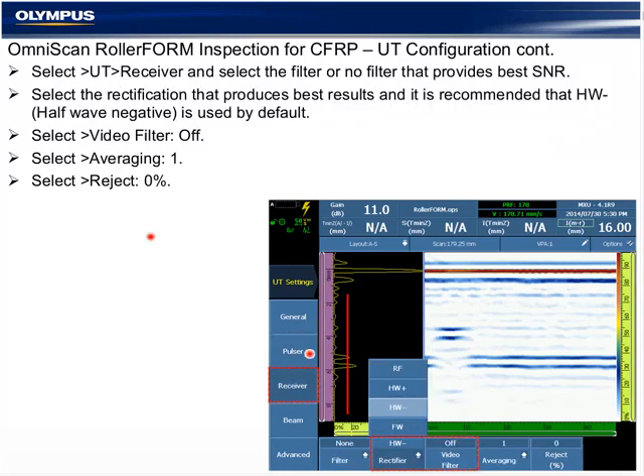Continuing the UT configuration to the receiver. The composite CFRP inspection is typically used in half-wave negative rectification, but use what works best through experimentation. There may be aluminum panels or other applications that would be better suited for that. Typically, video filter is off, so we don't get a smoothing effect between the multiple amplitude peaks of the interface, or it doesn't attempt to smooth the individual layers in the composite inspection. Averaging and reject maintain the defaults.